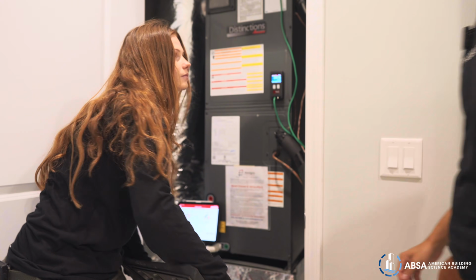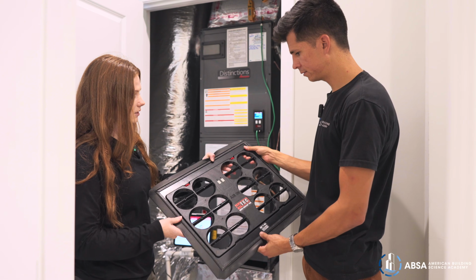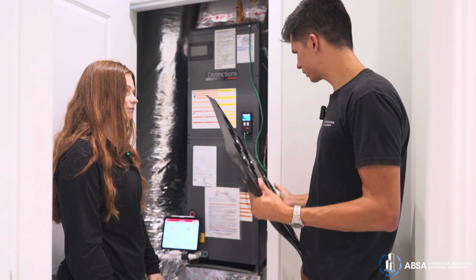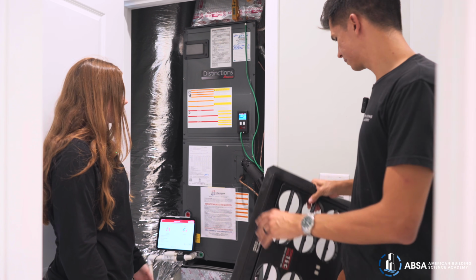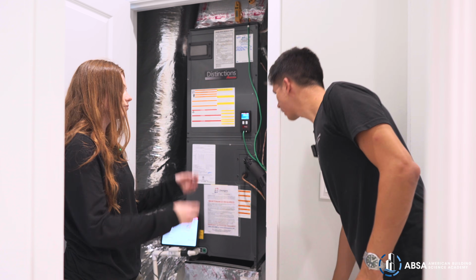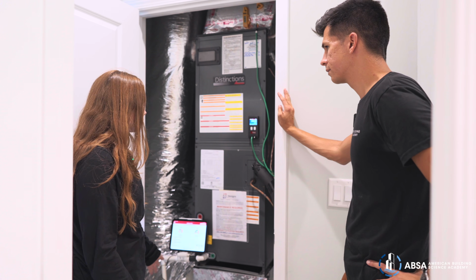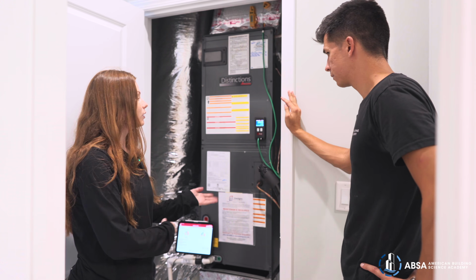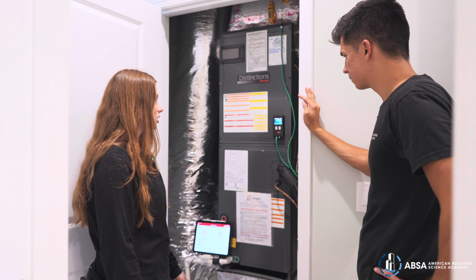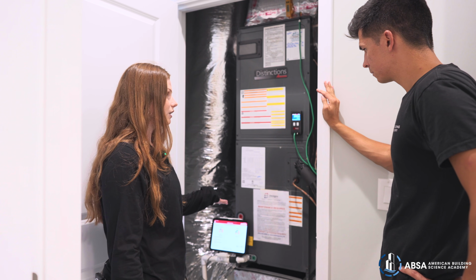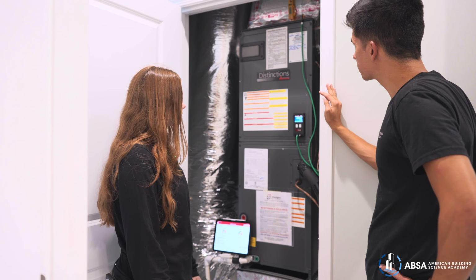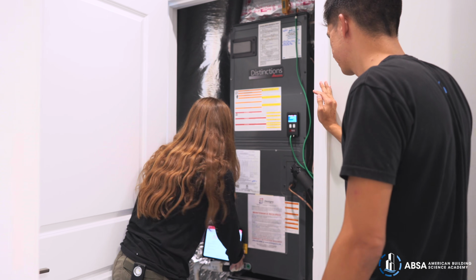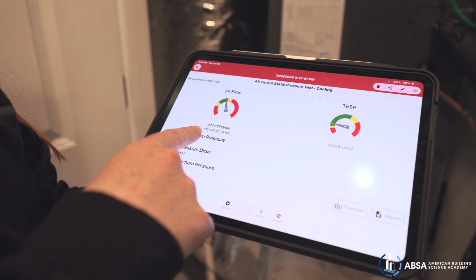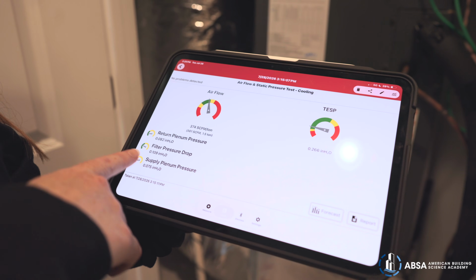Hey Reagan, so what you got here? What are you working on? This is the TrueFlow grid. Okay, and what does it do? It's going to measure airflow and static pressure of the unit. Okay, and why is that important? Airflow is going to tell us if it's cooling and drying properly. Static pressure is just going to tell us how hard the unit is working. Okay, and what's up with this unit? What's the verdict? Everything looks pretty good. The airflow is where we want it. Static pressure looks good. Filter pressure drop is also good.